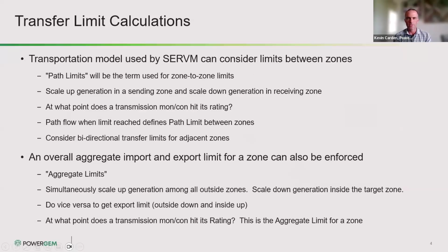Once we have those 8 zones, the next step was transfer limit analysis. We proportionally scale up generation in the sending zone and scale down generation in the receiving zone to identify how much swing we have before we hit a binding constraint. We're looking primarily at overloads - where do we hit an overload on a particular path? Once we have a binding mon-con pair, we identify that as the transfer limit. Whatever the aggregated transfers are in that scenario defines the transfer limit we put into SERVM.